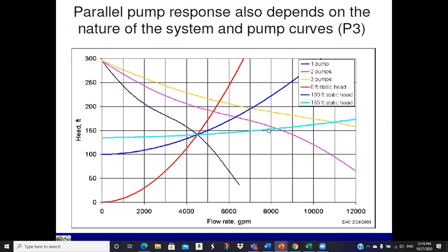The static dominated curve, again, is pretty good. One pump, two pumps, it doesn't quite double, but we get 4,500 here, that's probably 3,000, 3,500, and then we jump out to here with three. So it works fairly well, significantly better. When you run an additional pump, you get a significant increase in the amount of flow. Okay.